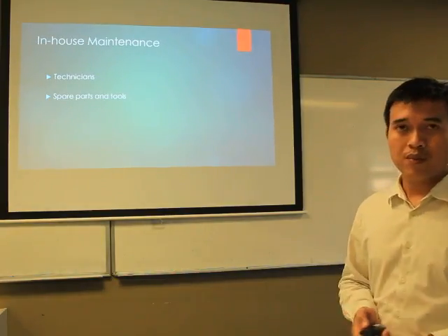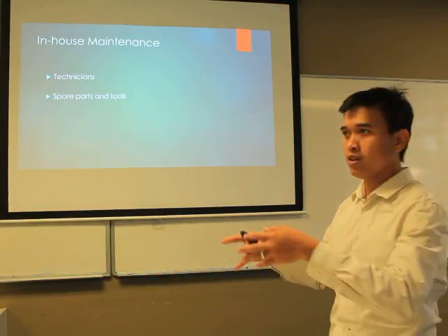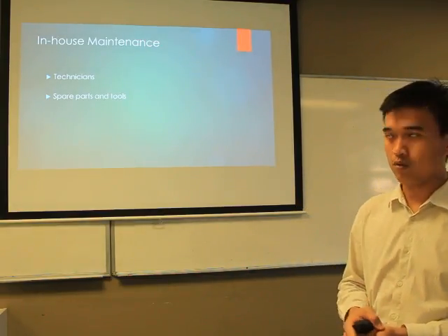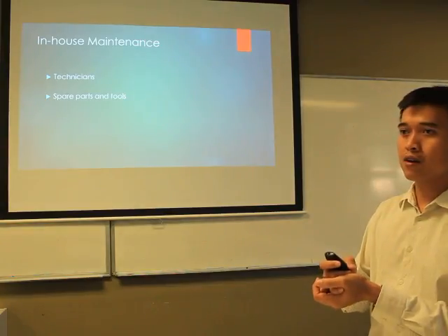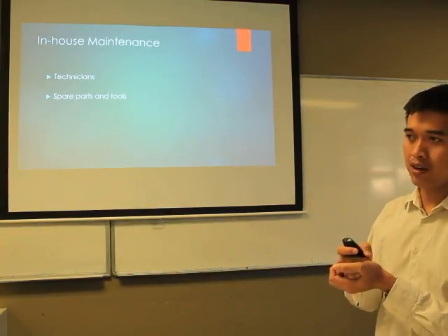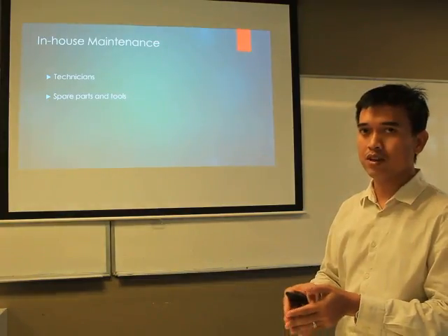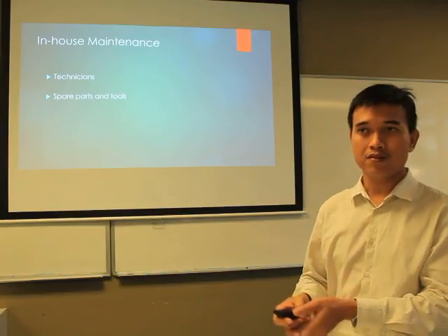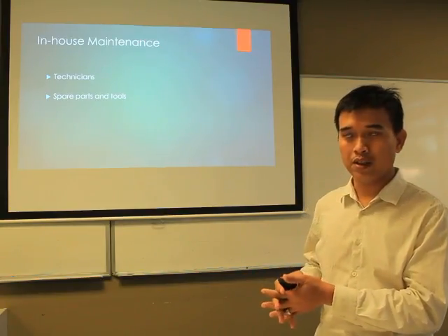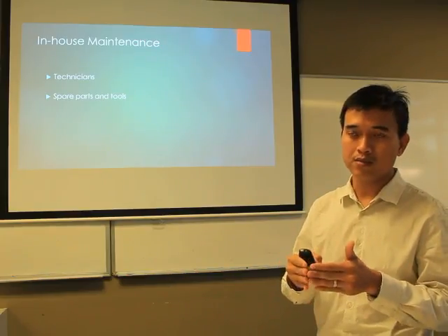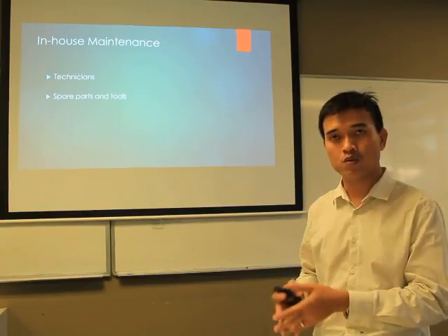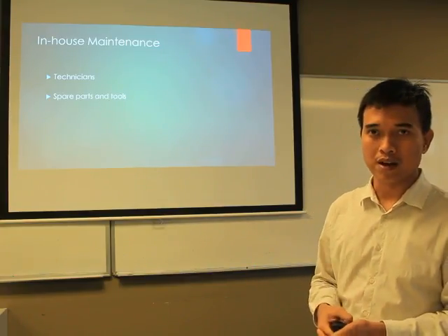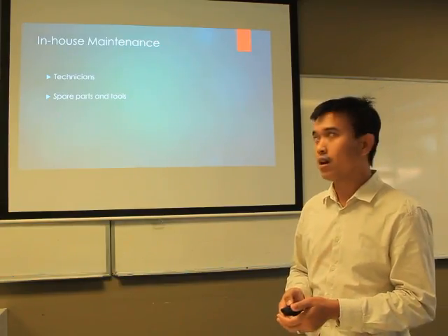In-house maintenance refers to the maintenance done by our own technicians in the hospital. Considering that we need to conduct it in-house, we need to know the number of technicians and their expertise for doing the work. And then we need to think of the spare parts. Do we have the warehouse to store the spare parts, or are the spare parts available in the local market, or do we have to purchase them?